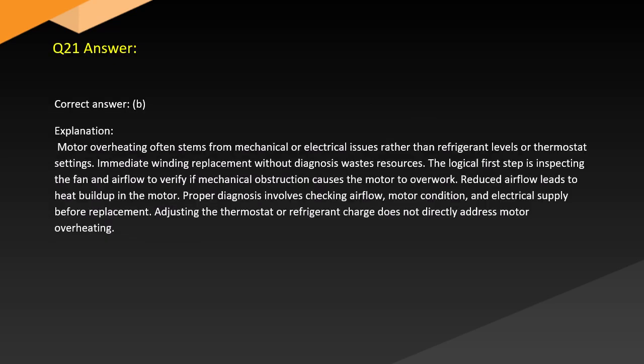Answer. Correct answer: B. Explanation. Motor overheating often stems from mechanical or electrical issues rather than refrigerant levels or thermostat settings. Immediate winding replacement without diagnosis wastes resources. The logical first step is inspecting the fan and airflow to verify if mechanical obstruction causes the motor to overwork. Reduced airflow leads to heat buildup in the motor. Proper diagnosis involves checking airflow, motor condition, and electrical supply before replacement. Adjusting the thermostat or refrigerant charge does not directly address motor overheating.